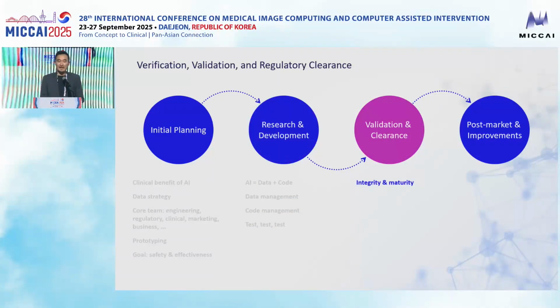Alrighty, and now let's say you feel comfortable about the performance of your system, okay? What you need to do is freeze all the elements to prevent further changes and enter the verification and validation phase. The way validation works is that you pre-specify test plans, meaning you write documents describing how you will test your device or your system. Once you write the plan, you execute the plan as written, get the result, and report the outcome. The report says whether your algorithm passed the test or not, and this is determined based on the statistical testing as defined in the plan. And as you can see, you need to adhere strictly to the plan.